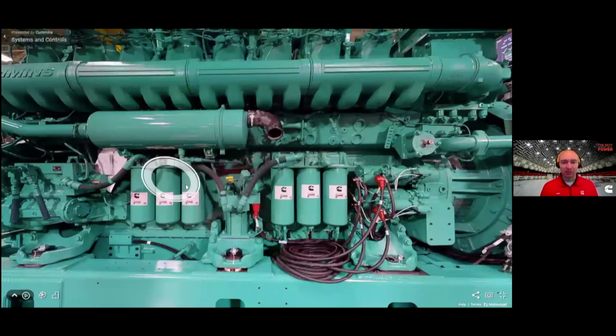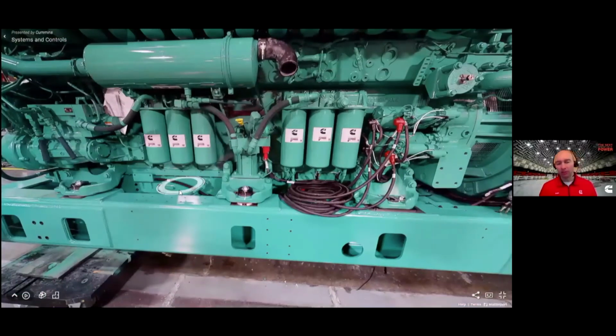It's a high-speed diesel, runs at 1800 RPM. The design is capable of a 500-hour service interval, and we achieve that with significant oil pan capacity, in addition to fuel filtration and oil filtration that can handle that kind of duration.